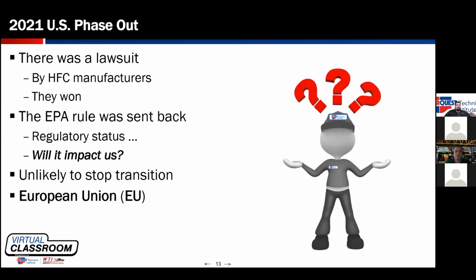Other manufacturers that make R134A that do not hold the patent to make 1234YF for automotive use sued the EPA. They stated that the EPA overstepped their authority, that the Clean Air Act gave the EPA the authority to regulate, or excuse me, ozone depleting refrigerants. It did not give them the authority to regulate refrigerants with high global warming potential. They won. The rule was sent back. It has been appealed. The EPA was supposed to issue a new rule earlier this year. As far as I know, it has not been issued yet. That said, it is very unlikely that manufacturers are going to go back to R134A at this point in time. It is likely that we will still see the transition to R1234YF happen and continue to happen.